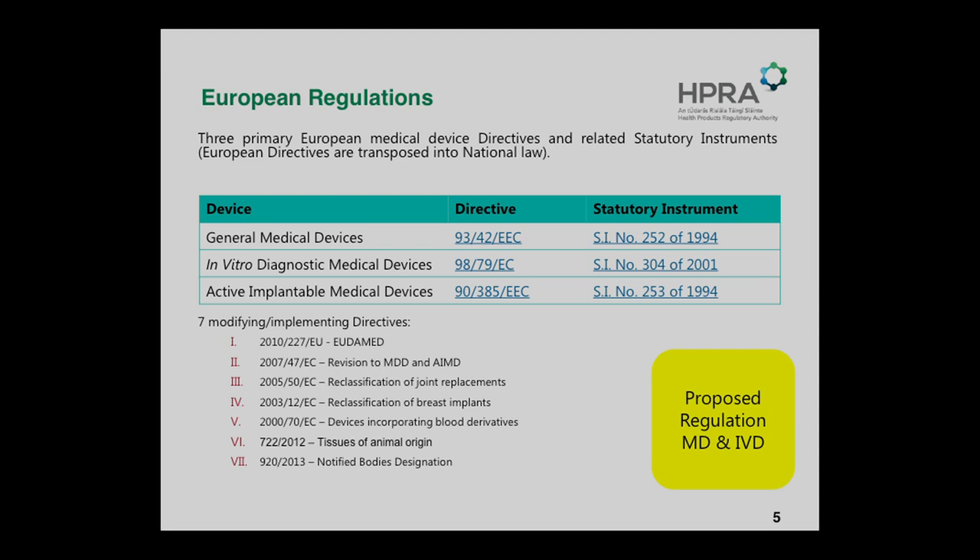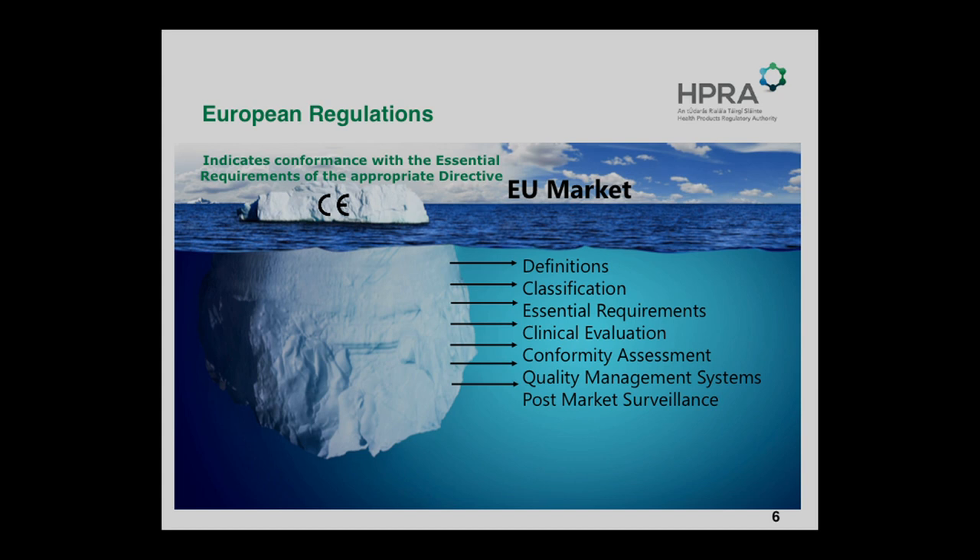I'm going to talk more about general medical devices. For general medical devices we have four main risk categories. There are low-risk Class I devices, which are self-declared and maintained in a register. We have Class IIa and Class IIb devices — an example of a Class IIa device would be a contact lens used not on intact skin but on broken skin or in the eye. Class IIb devices would include peripheral bare metal stents — implants in the peripheral regions. Class III devices are those in the central nervous system or the cardiovascular system, such as drug-eluting stents and orthopaedic hips.